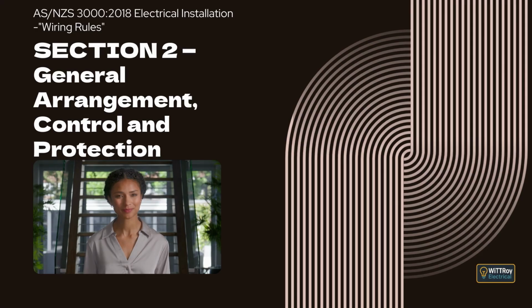Clause 2.3.6.3, Installation. The device used for shutting down must be installed in the main circuit so it properly removes the supply to the mechanical parts. It must be positioned so that the relevant conductor is safely interrupted. Clause 2.3.6.4, Identification. Any device used for shutting down during mechanical maintenance must be marked clearly so that workers know exactly what it isolates. It must be easy to find and convenient to use in a maintenance situation.